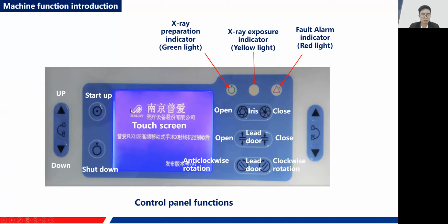Okay, we go to the control panel. Right here, we can see we've got many buttons, a screen, and 3 lights. From the left, the green one is the X-ray ready indicator. The middle one, the X-ray exposure indicator, is a yellow one, and the right one is the fault alarm indicator, so it will be red when something goes wrong. And of course, the up and down control buttons, and there are two of them that function exactly the same. And the startup button: the one with a dot within the circle is for powering on, and the one with a dot outside of the circle is for shutting down the C-arm.